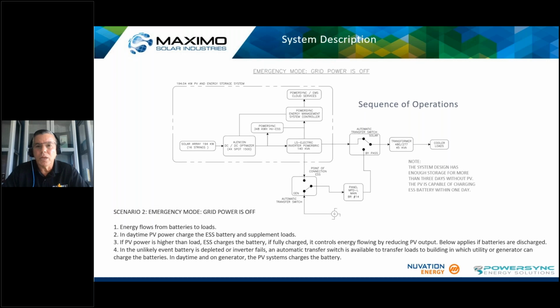Now, what happens when the grid goes off is you have an off-grid system pretty much. The system will continue to monitor for power coming back from the grid, but in the meantime, it will be using all that energy to power the loads. In reality, because the load was less than expected from the original design, this system can operate for over 3 days on batteries. And as we have 4 MPPT optimizers, the all-in-one equipment, it would require all of them to fail, or the main disconnect to fail, to stop the PV power from going into the system. So this is a very, very well-designed system. Next slide.